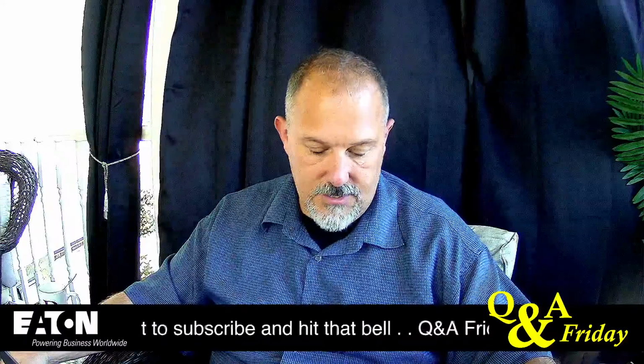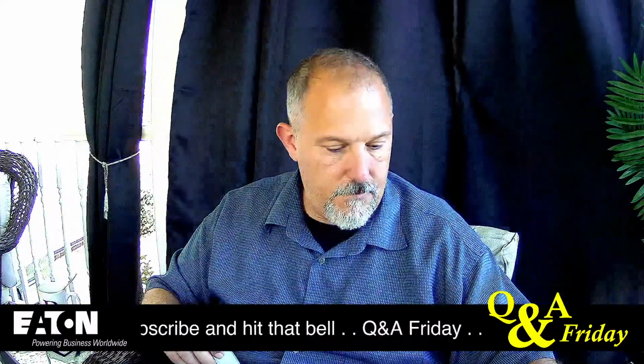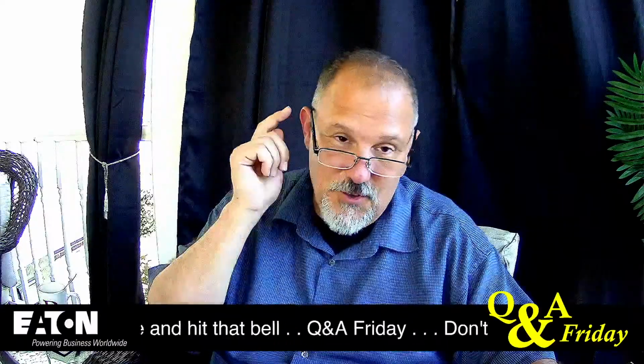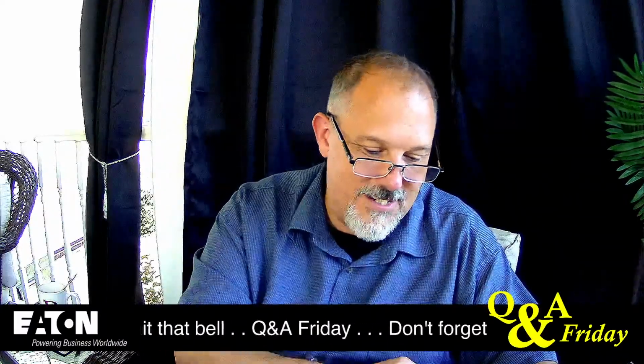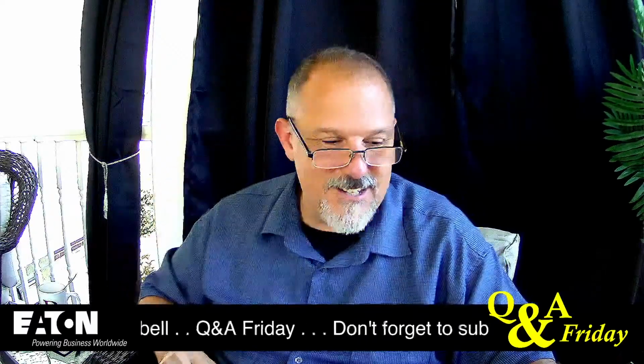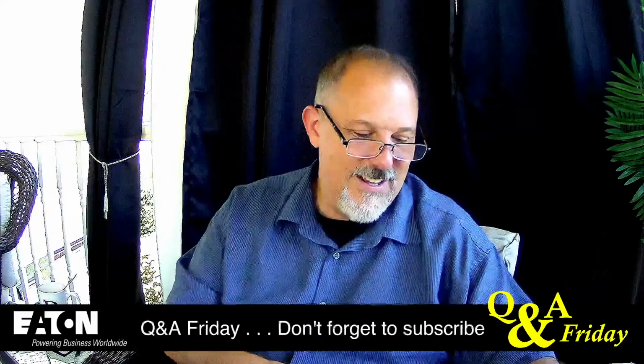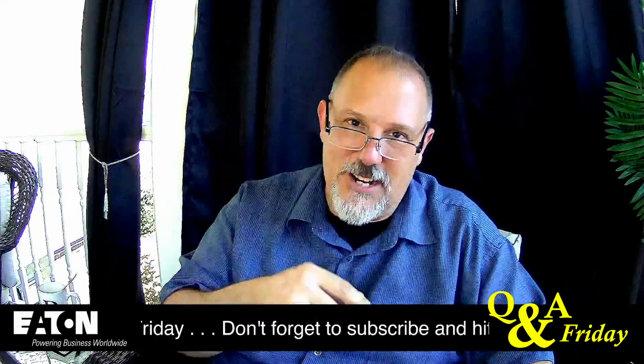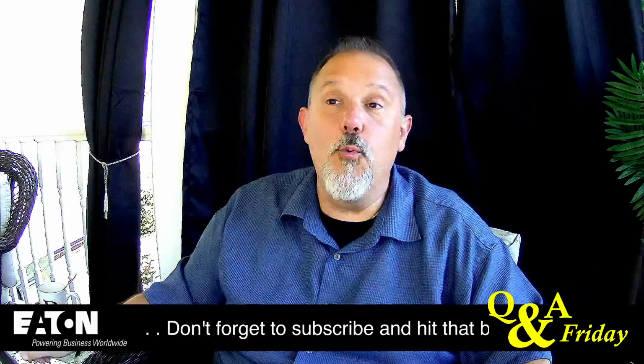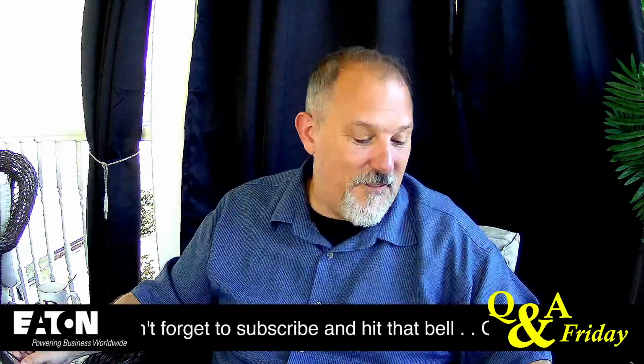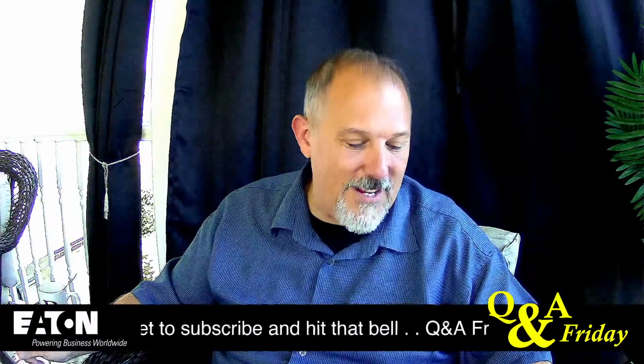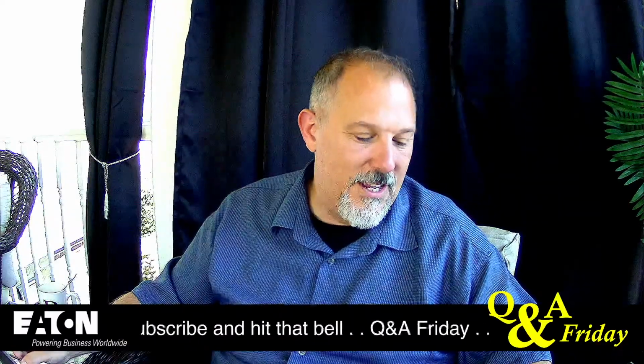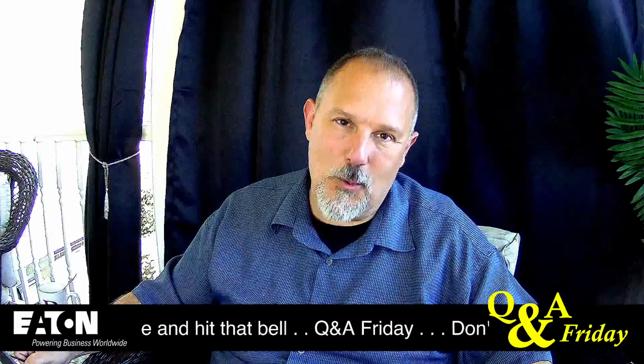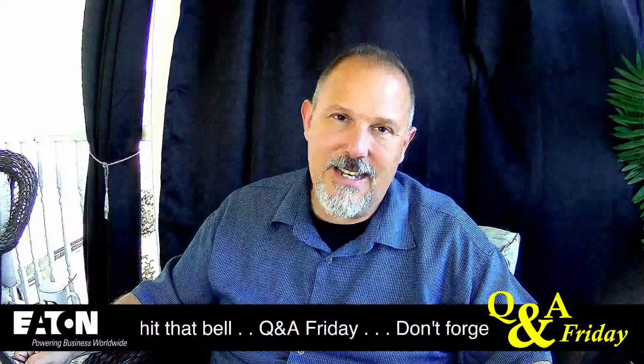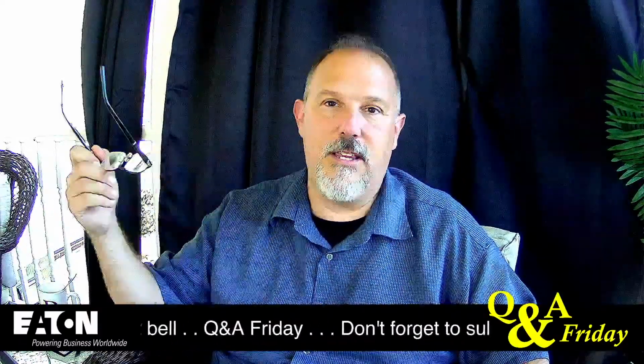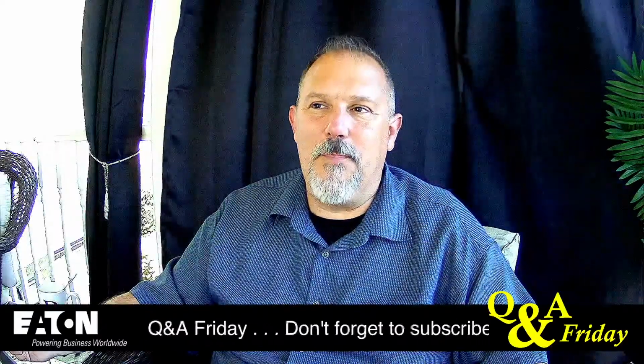So 250.24C, I believe it is. Yep, 250.24C. And then if you look at the code book, 695.6, power wiring, A1, I don't know how I missed this. The informational note, this is like the icing on the cake that you really had a bad day. The informational note says 250.24C for routing the grounded conductor to the service equipment. So you've got to go back and look at 250.24C. Man, I'll tell you what. Sometimes, it's one thing to just say, hey, this is what we do. But it's those questions of why.